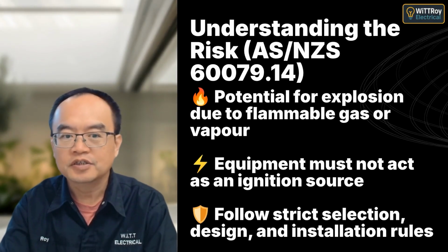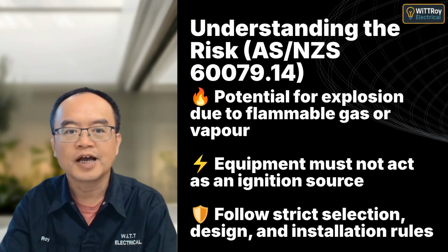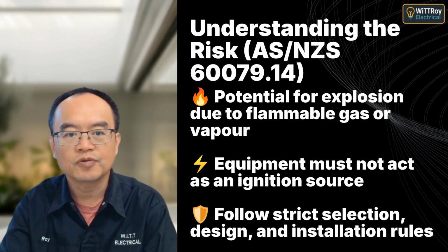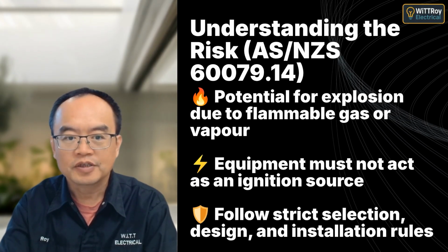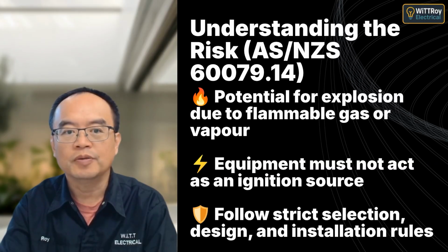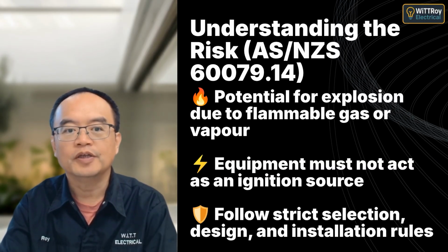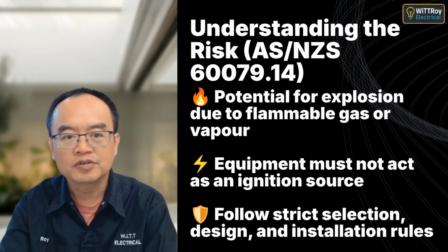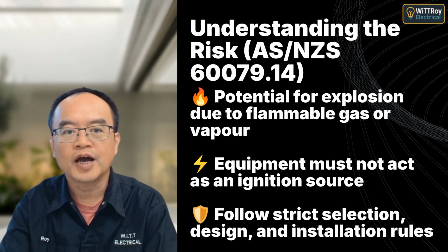AS/NZS 60079.14 highlights that hazardous areas contain flammable gases or vapors that can ignite. Inspectors must ensure equipment used does not become an ignition source. Applying correct installation techniques and selecting certified equipment reduces the risk of fire or explosion.